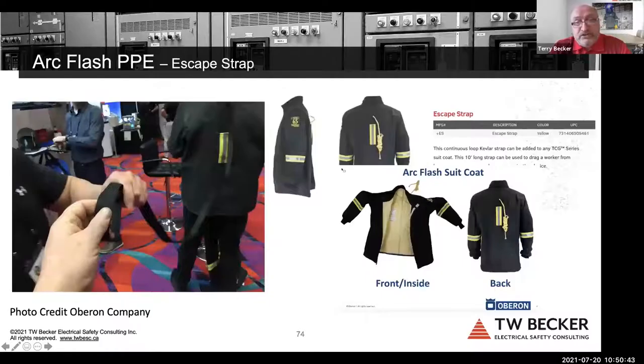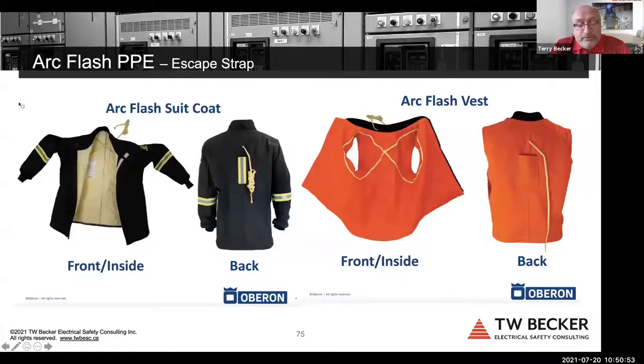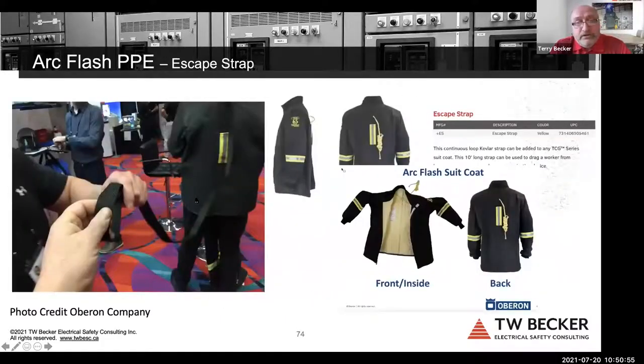This is huge. Last year, Oberon brought out the escape strap, right? So it's embedded right in an arc flash suit. You can see the X where it's braced to be able to grab the worker from the standpoint of weight. And this escape strap is brought out. So you don't need a rescue hot stick anymore when you need 2 workers for high voltage work predominantly. You can use the escape strap. I think this is an amazing innovation from Oberon. You may not be aware of it.